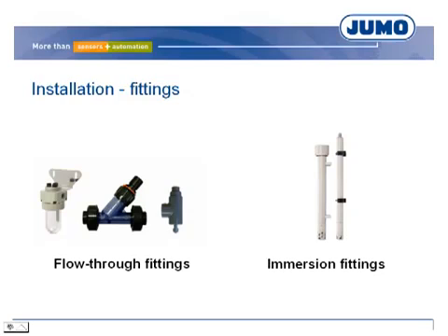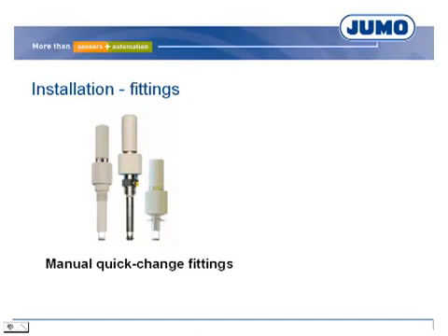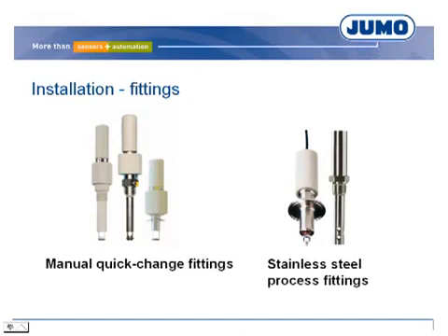Immersion fittings are mounted into open channels or tanks, shielding the electrode from breakage, with measurements possible at different depths. Manual quick-change fittings are used for pH measurement in closed circuits or in the inflow or outflow of wastewater systems; they can also be laterally installed in tanks so the sensor can be removed without emptying the tank. Process fittings made of stainless steel can be installed directly into stainless steel pipe systems or tank walls, mainly in procedural plants with increased hygienic requirements.